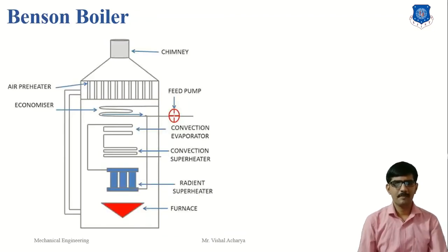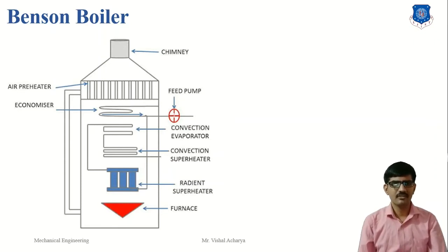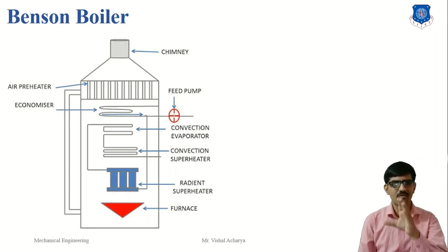What is the Benson boiler? Benson boiler is a high pressure drumless supercritical water tube steam boiler with forced circulation, invented in 1922 by Mark Benson. This boiler is a supercritical boiler in which the feed water is compressed to supercritical pressure, which prevents the formation of bubbles on the water tube surface. The bubbles do not form because at supercritical pressure the density of water and steam becomes the same.